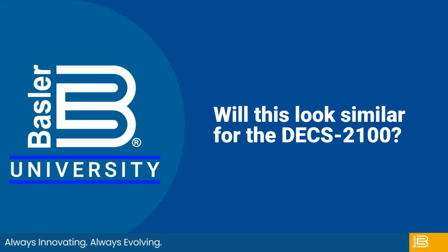Somebody asked, is this going to look similar for the DECS 2100? So as I was mentioning in that presentation, this software is used with our DECS 150, 250, 250N, 250E, and 450. We also have a DECS 2100, which is an even higher-end exciter system that goes above the capabilities of the DECS 450 systems. That DECS 2100 software looks similar, but is very different. Instead of using BESTCOMSPlus, it uses software called BESTCOMS Pro. As such, there is a lot more programmability, a lot more capability in the DECS 2100. And so we are very cautious about who we allow to actually program those, because if you're inexperienced with it, it can be very easy to create problems.